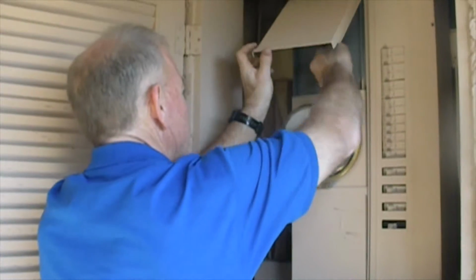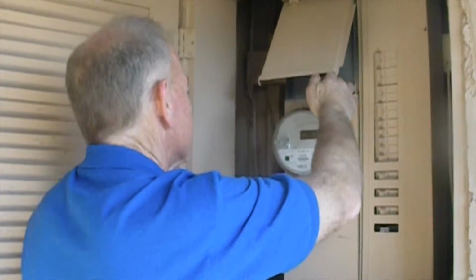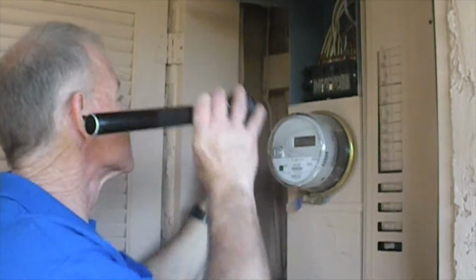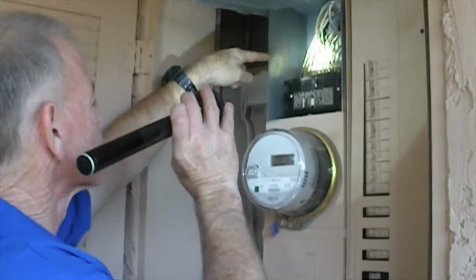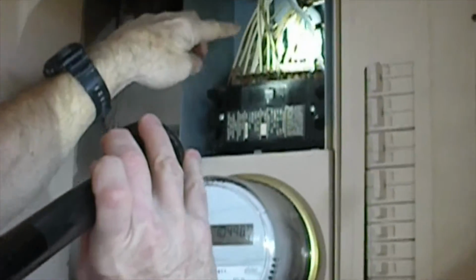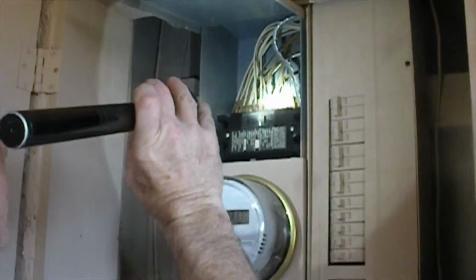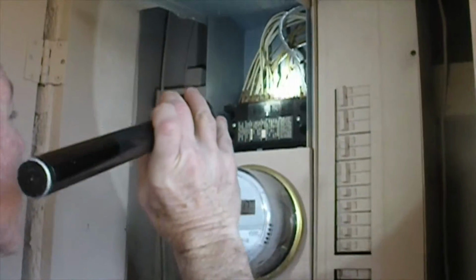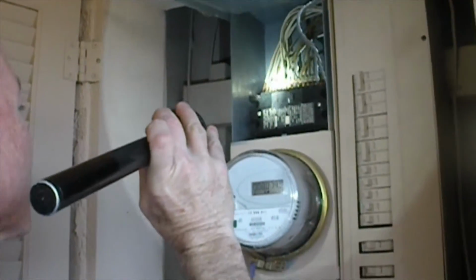We're going to take this inner cover off, and this is your main circuit breaker right here. These are your different connections, your ground and neutral wires. We're looking for any scorched or burned insulation, making sure connections are all nice and tight, and checking for corrosion.